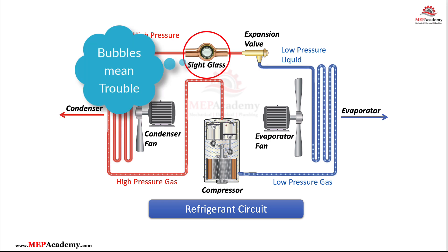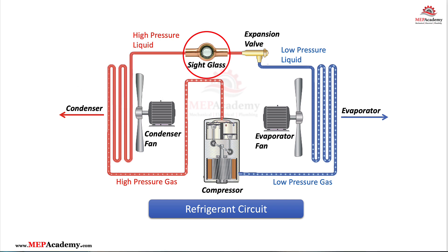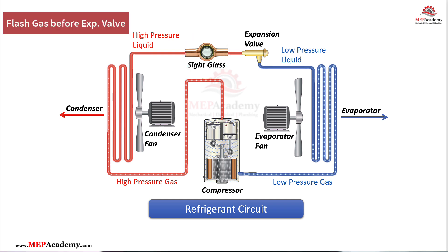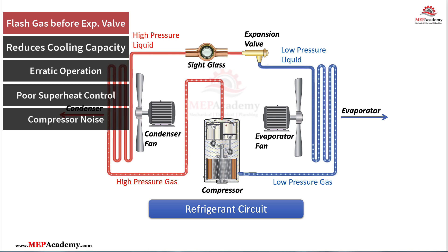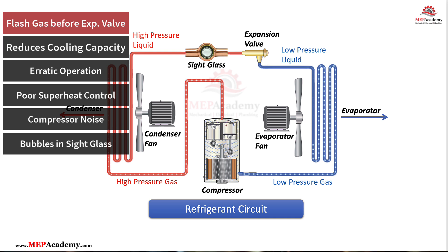Bubbles mean trouble. In the evaporator, flash gas is expected — it's part of the process. But in the liquid line, it's a big issue. Flash gas before the metering device reduces cooling capacity and causes erratic operation. You'll see the following symptoms: poor superheat control, compressor noise, and bubbles in the sight glass.